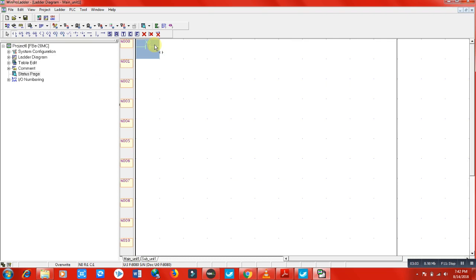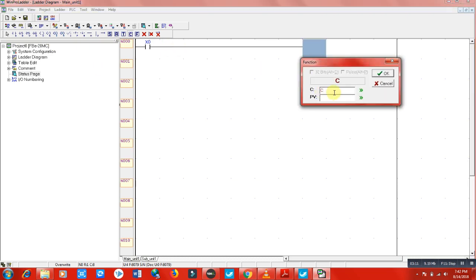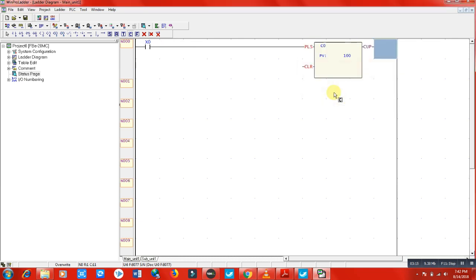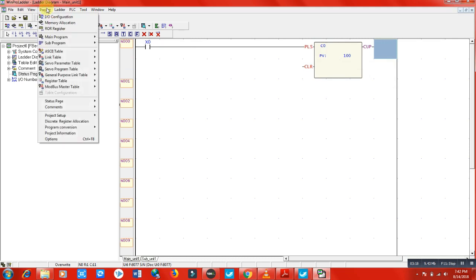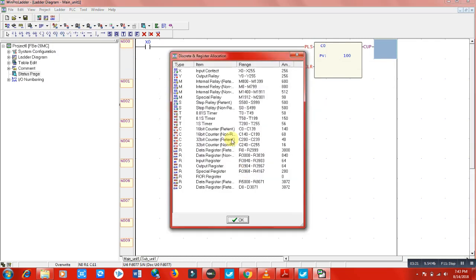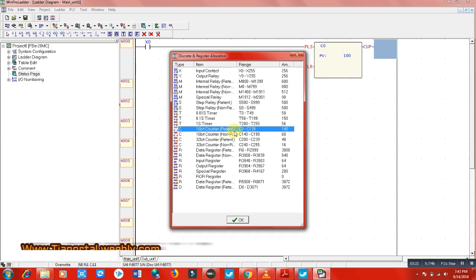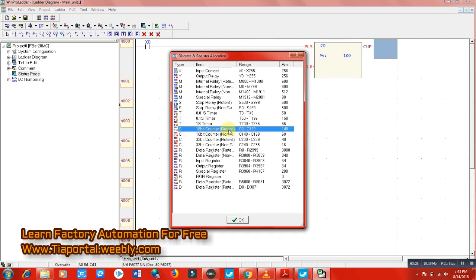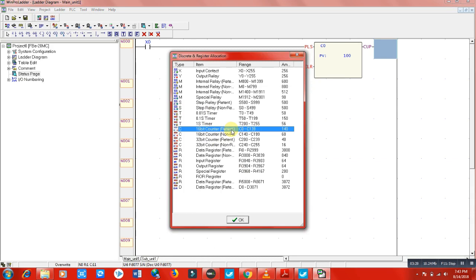Let's try this practically. I'll use X0 as a normally open contact and add counter C0 with a preset value of 100. C0 is a 16-bit retentive counter, which means it will remember its value and not start from zero every time. There are 140 retentive counters available in this PLC programming software.